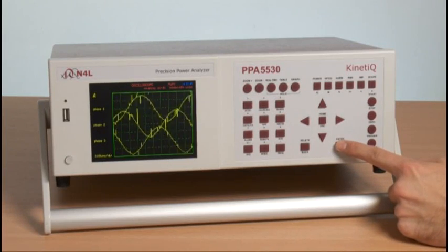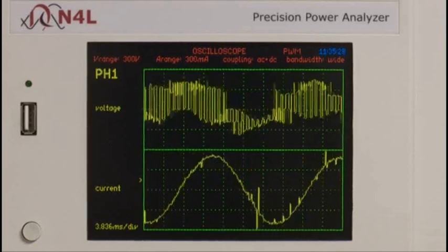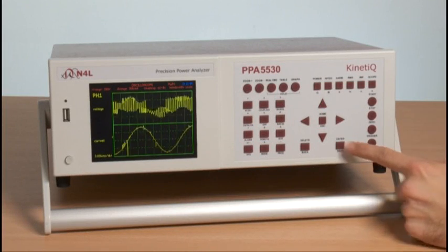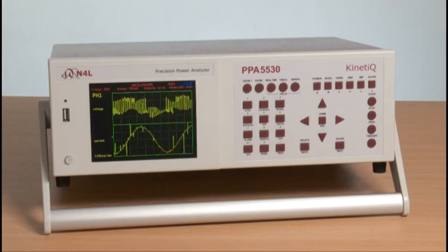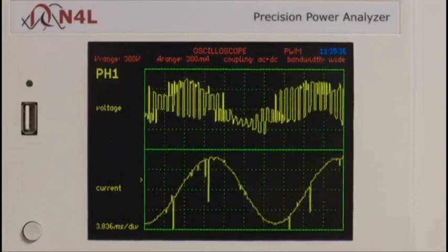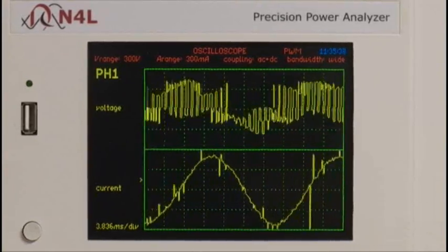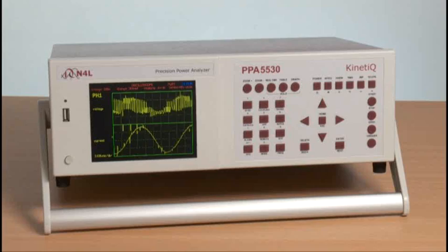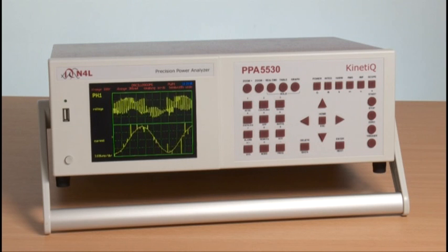By pressing next, we see the current waveform with a sinusoidal fundamental component and a large amount of noise. Moving to a single phase, we can see one phase with volts and current together. The switching frequency and its associated harmonic components make detection of the correct fundamental frequency very difficult for many power analyzers.